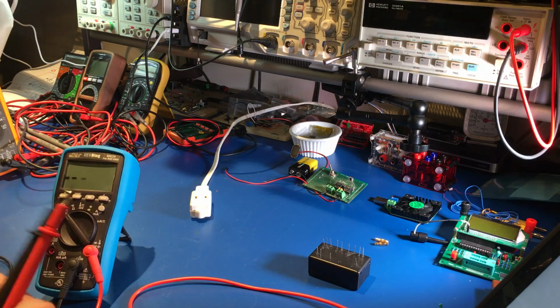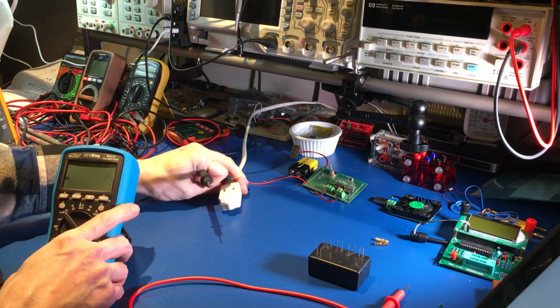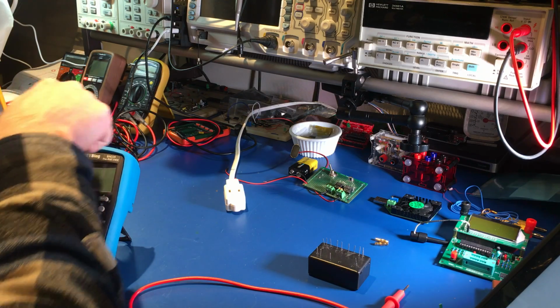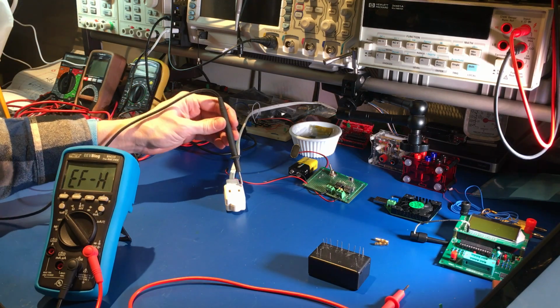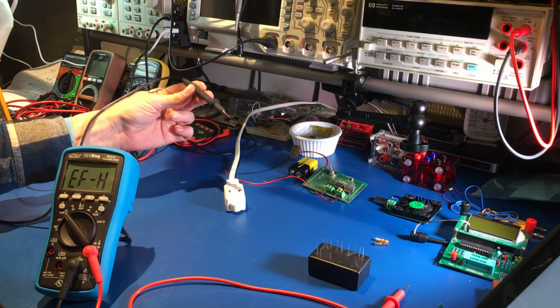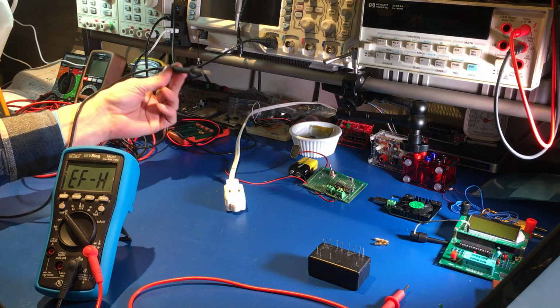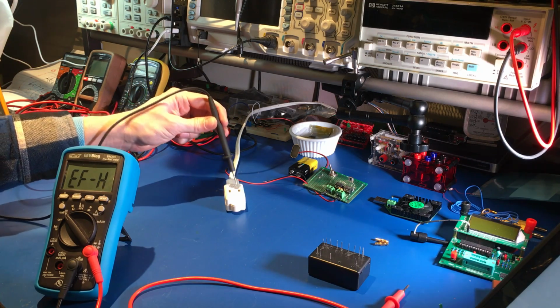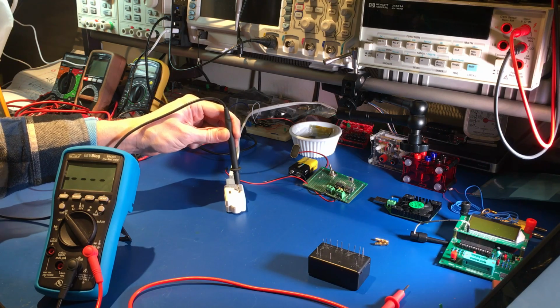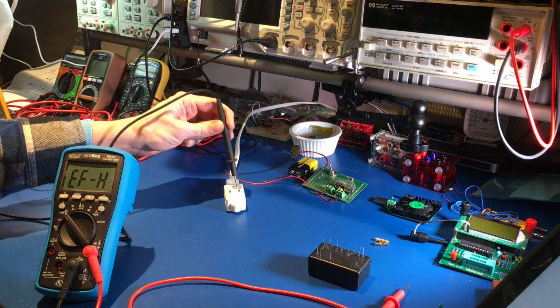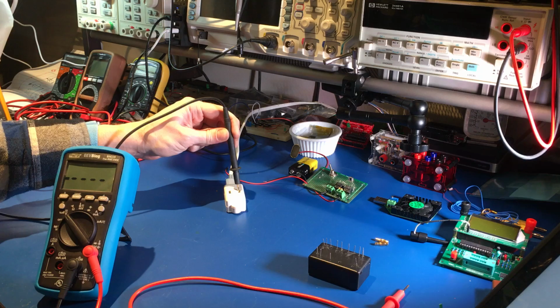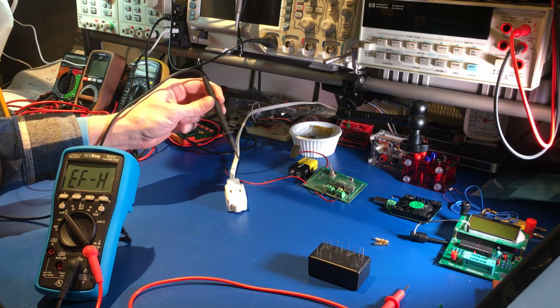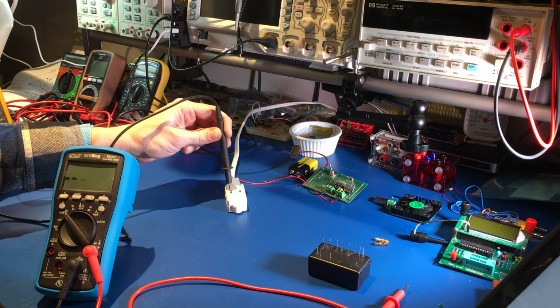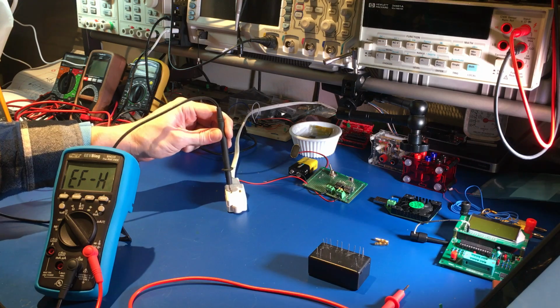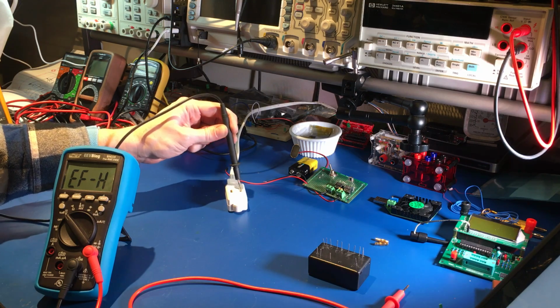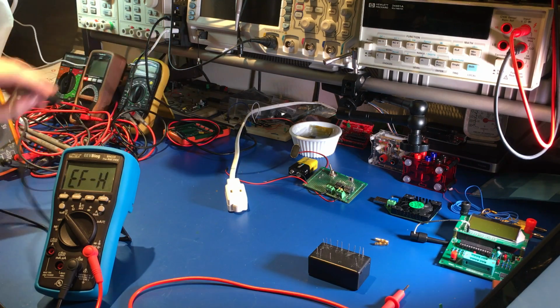But when you're using the probe, if you're actually looking for a live line, you're not using the field detection. You're going for a direct signal. This is why you don't need to use 2 probes to test which line is live. You don't need to have 2 hands in it. You can actually use a single hand. There it is. Boom. All 5 bars, constant tone. That's a live line. That picked up a little interference, but there it is, live line.